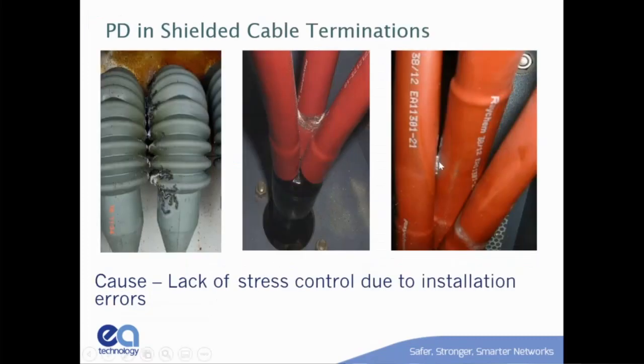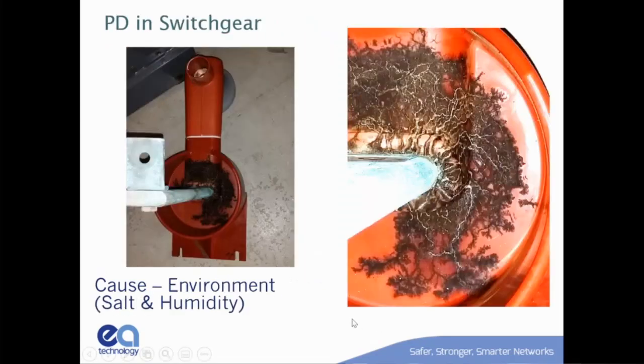Again, more typical things, cable terminations. Once you peel that shield back, you can't get those cores that close together. Classic problem here, typical problems you see with trifurcated cables.